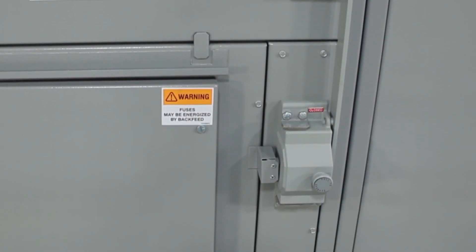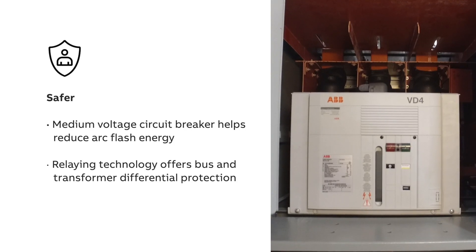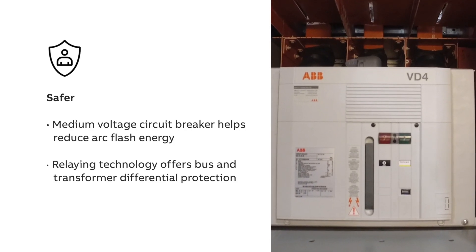An optional Kirk key interlock system is available to further enhance safer lockout/tagout operations. For additional protection, the optional UFES ultra-fast earthing switch provides extremely fast arc interruption. An optional Brake Master MD remote monitoring and diagnostics solution facilitates routine operation outside the arc flash boundary.